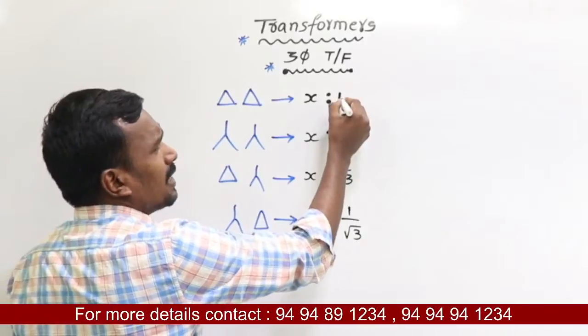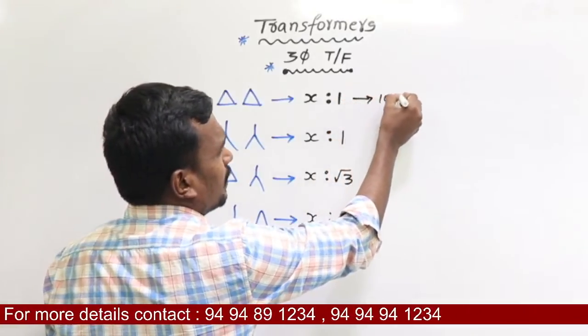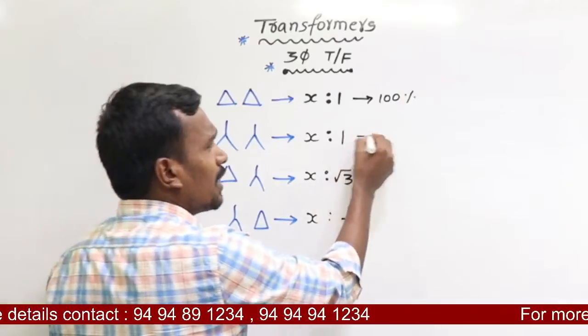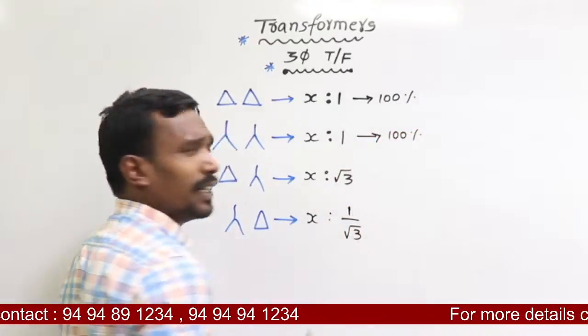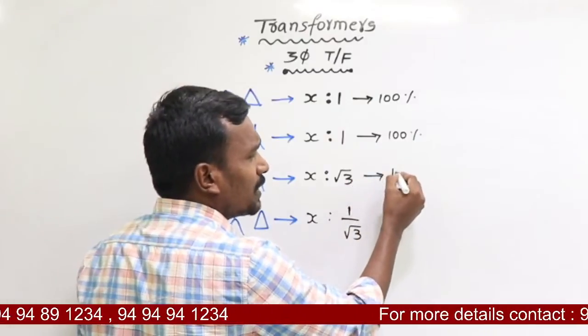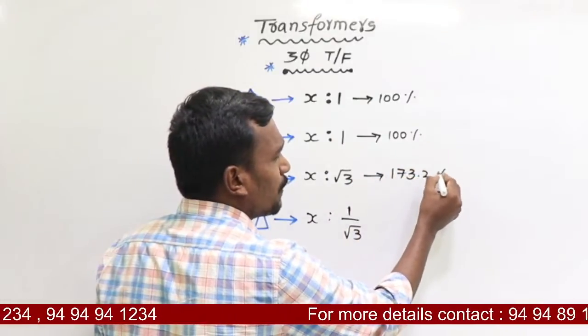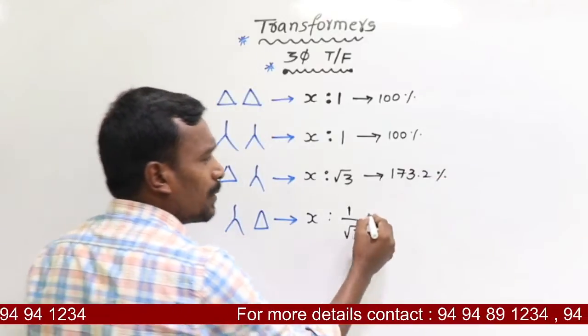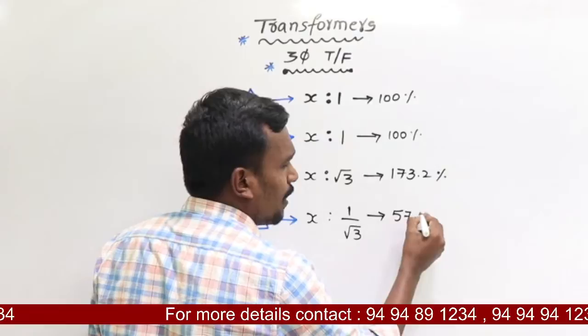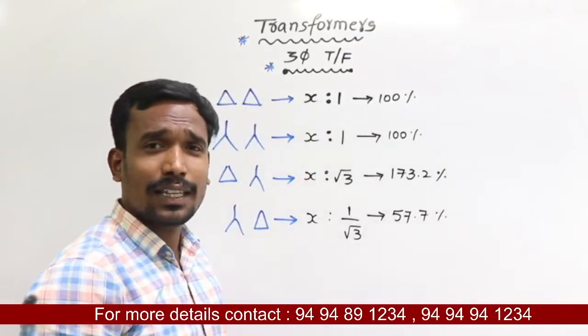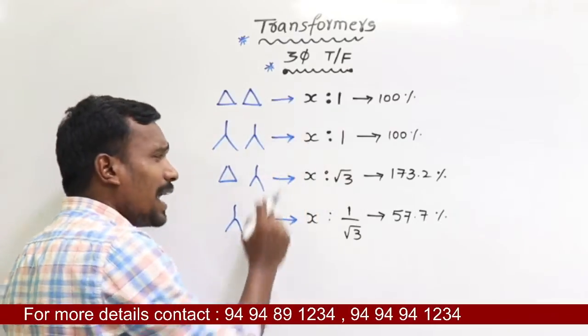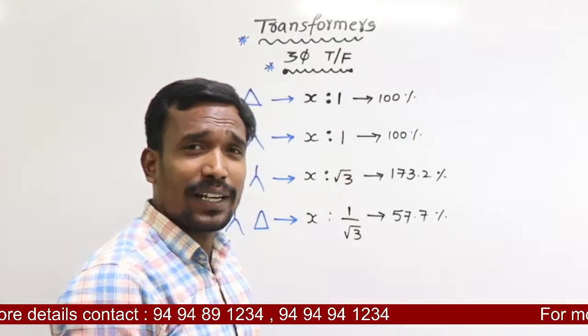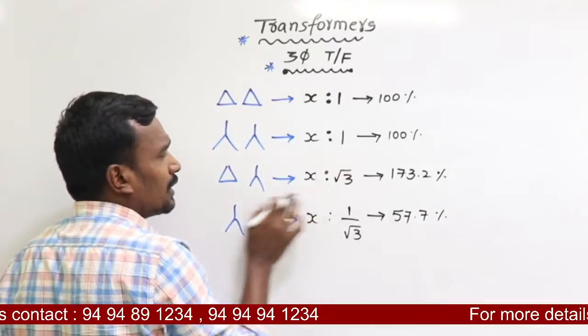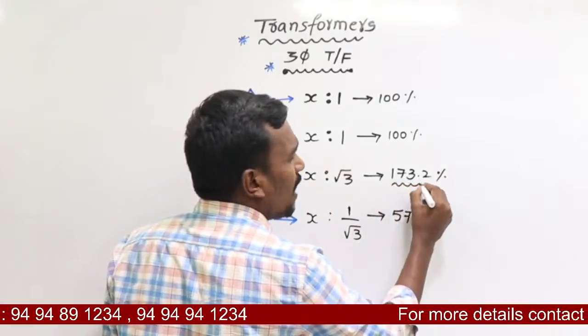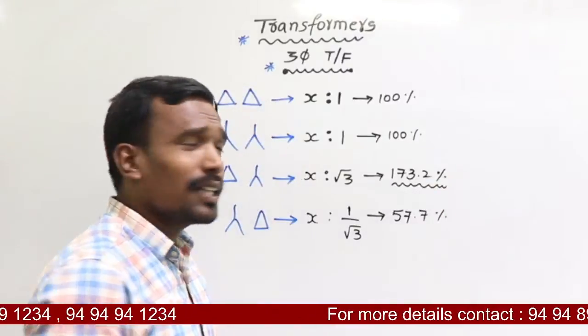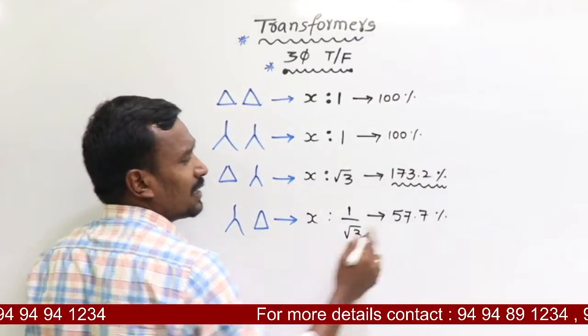For example, taking the output as 1, that's 100%. For root 3, that is 173.2%. For 1 by root 3, that is 57.7%. So for the same number of phase turns, the output voltage for delta-star is 173%, while for star-delta it is only 57.7%.